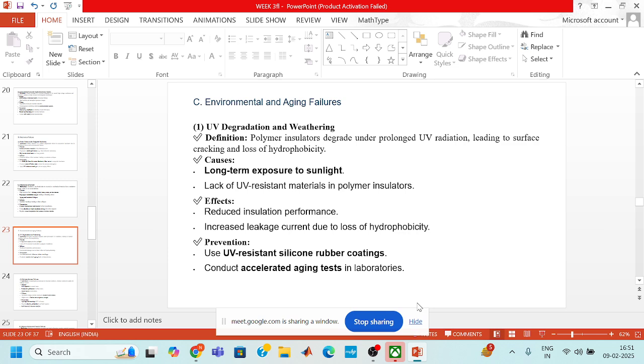In environmental and aging failures, we see UV degradation and weathering. Polymer insulators degrade in performance under prolonged UV radiation, leading to surface cracking and loss of hydrophobicity. Long-term exposure to sunlight and a lack of UV resistant materials in polymer insulators can cause UV degradation. Due to this, insulation performance is reduced, and leakage current increases due to the loss of hydrophobicity. To prevent this, we have to use UV resistant silicone rubber coatings, and conduct accelerated aging tests in laboratories.